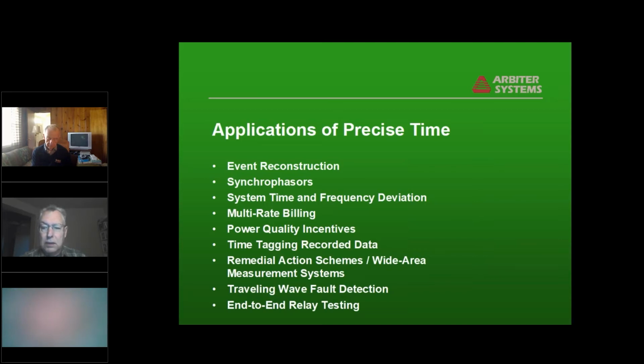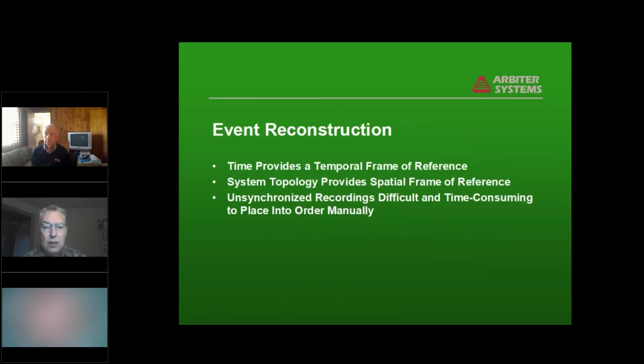And end-to-end relay testing, when you're actually testing relays on both ends of the line, you need to be able to generate some sort of synchronization between the test sets at the two ends. So it's just a few applications. Talk a little bit more about each one.